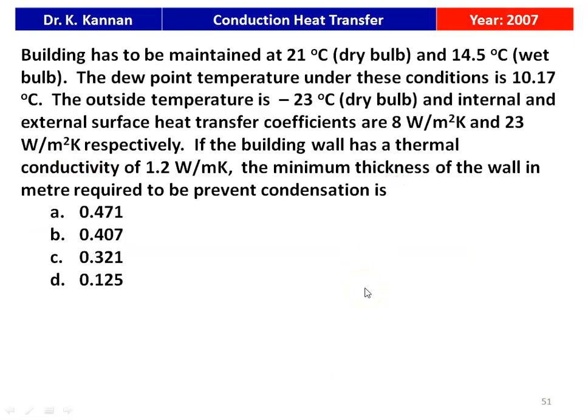The next question from the 2007 question paper: a building is maintained at 21°C dry bulb temperature. The dew point temperature is 10.17°C. Outside temperature is −23°C. Internal and external surface heat transfer coefficients are 8 and 23 W/m²K respectively. Thermal conductivity of wall is 1.2 W/mK. The minimum wall thickness to prevent condensation is required. The wet bulb temperature is not needed for this calculation. The correct answer is 0.407 m.